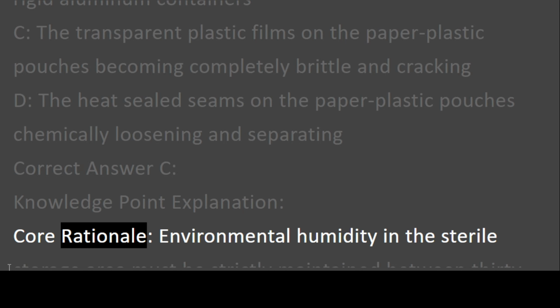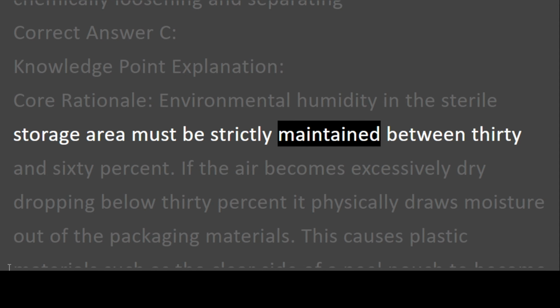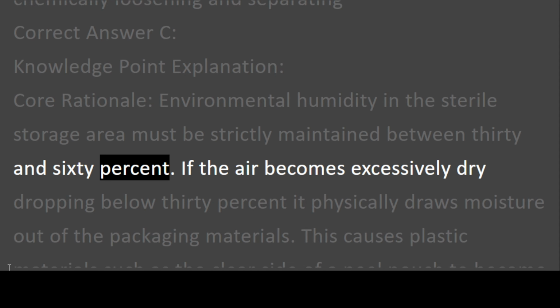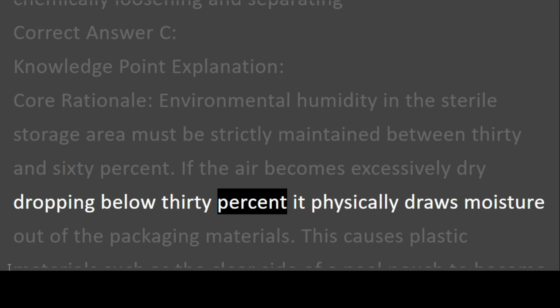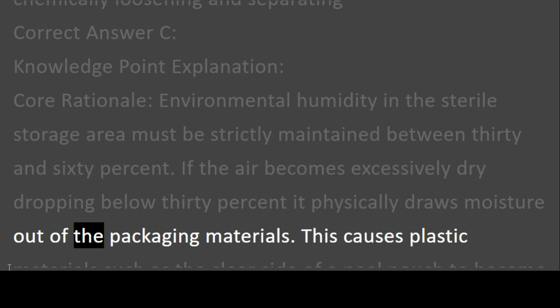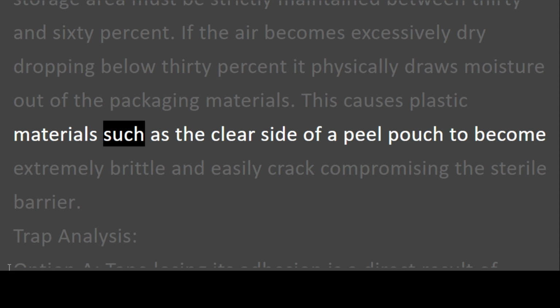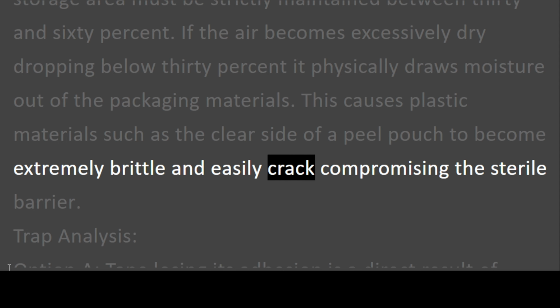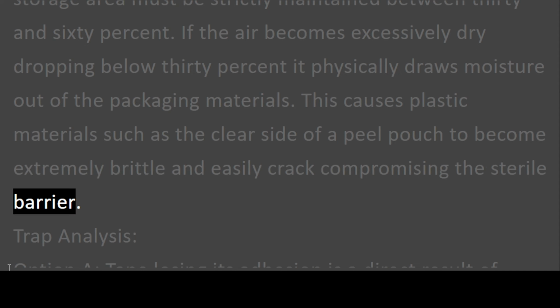Core rationale. Environmental humidity in the sterile storage area must be strictly maintained between 30 and 60%. If the air becomes excessively dry, dropping below 30%, it physically draws moisture out of the packaging materials. This causes plastic materials, such as the clear side of a peel pouch, to become extremely brittle and easily crack, compromising the sterile barrier. Trap analysis.